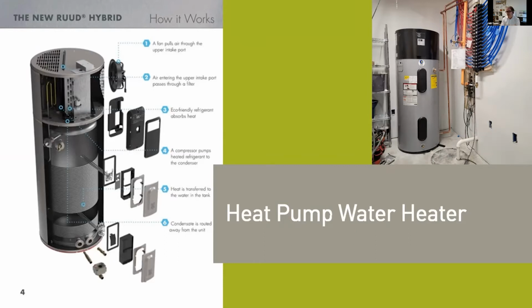In this case, we have a mechanical room that was just below the minimum size. There are venting kits that you can add to this to improve the circulation and the performance. The jury's still out. We may need to add that depending on how the performance goes, particularly in the cooler months. But this is one of the key features in terms of what that energy savings, where that comes from.